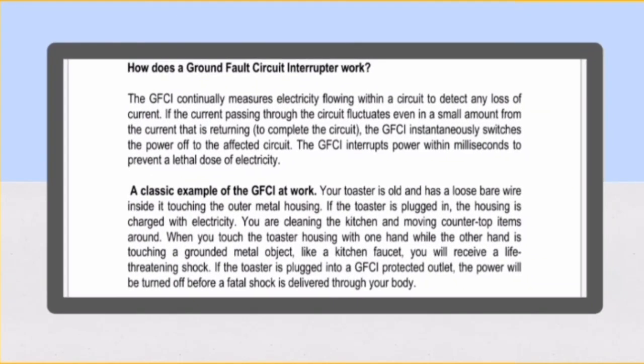How does a ground fault circuit interrupter work? A GFCI continually measures electricity flowing within a circuit to detect any loss of current. If the current passing through the circuit fluctuates even a small amount from the current that is returning, the GFCI instantaneously switches the power off to the affected circuit. The GFCI interrupts power within milliseconds to prevent a lethal dose of electricity.